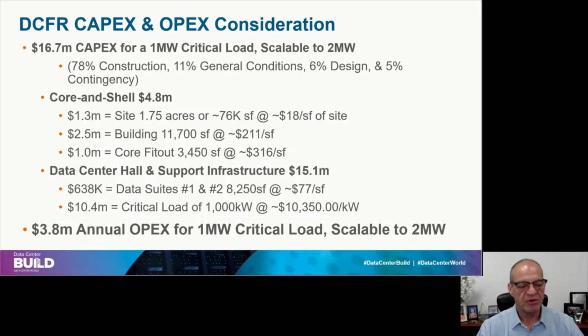Assuming you're building both suites out at the same time, the most critical number is the critical load cost, about $10,000 per kilowatt, which scales linearly with size, and by the way, this is at very small scale. At scale, we'll reduce that even further to compete with what we're doing, that $8 million a megawatt, trying to get even lower. That's typically done with a traditional design, but at much larger scale, 20, 40, 60 megawatts, before you can achieve those numbers, and you need the purchasing power of the most elite data center operators in the world.